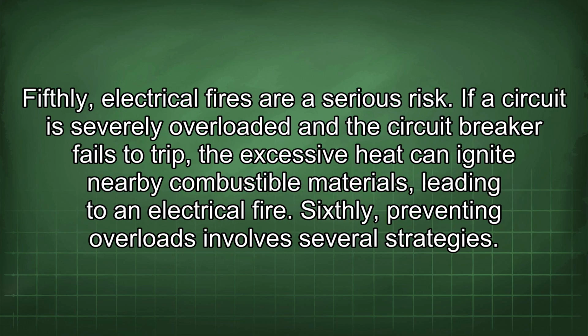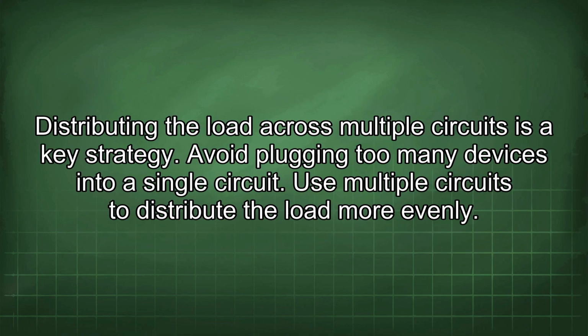Fifthly, electrical fires are a serious risk. If a circuit is severely overloaded and the circuit breaker fails to trip, the excessive heat can ignite nearby combustible materials, leading to an electrical fire. Sixthly, preventing overloads involves several strategies. Distributing the load across multiple circuits is a key strategy. Avoid plugging too many devices into a single circuit. Use multiple circuits to distribute the load more evenly.